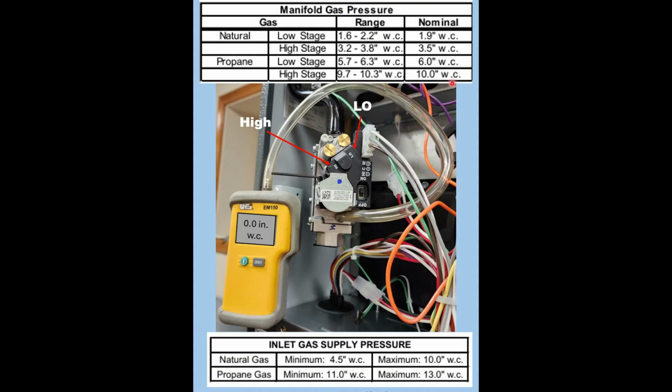And we see here we're hooked up to our outlet pressure boss here, our inlet pressure boss here to see what we got. And if you have a dual port manometer, you can check them both at the same time.